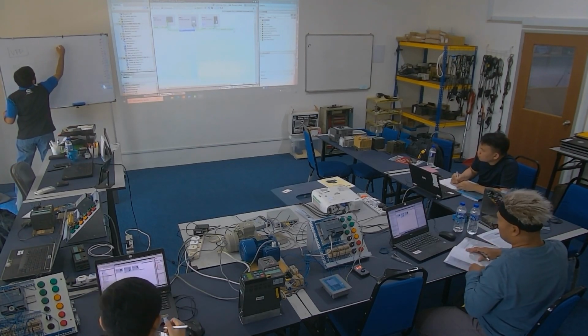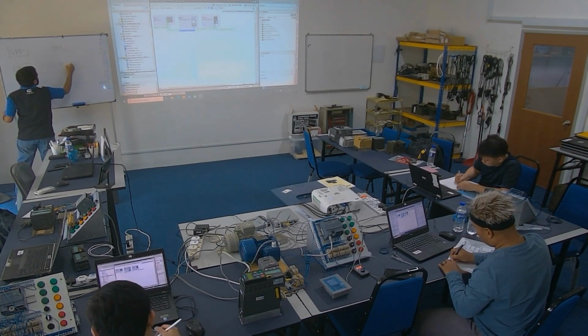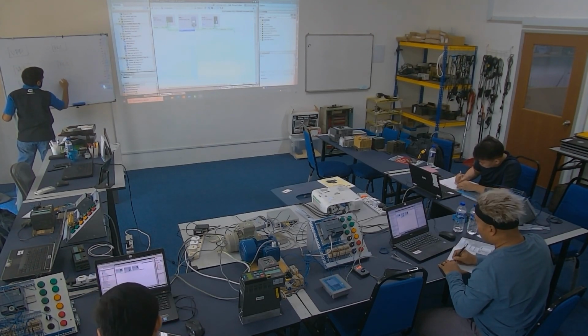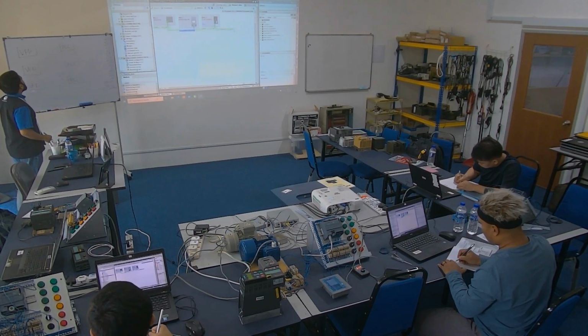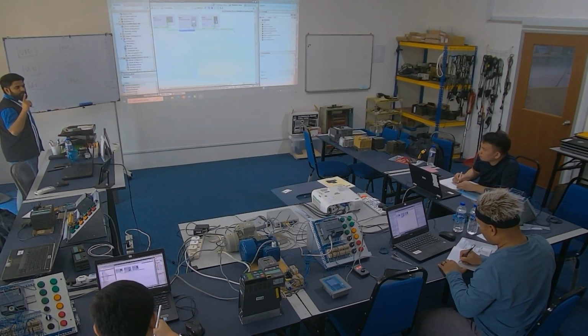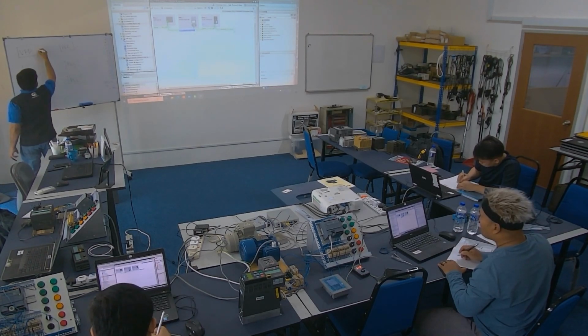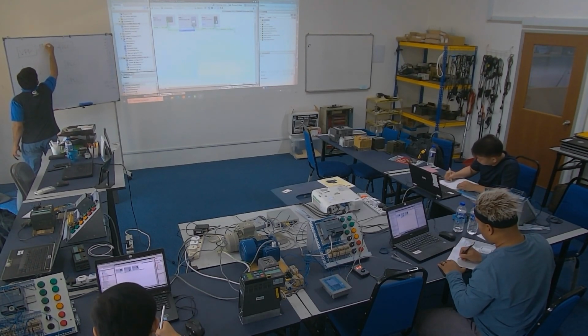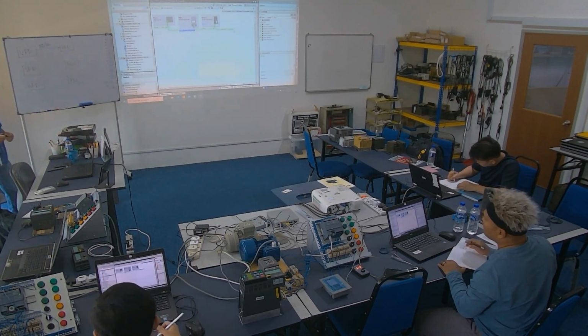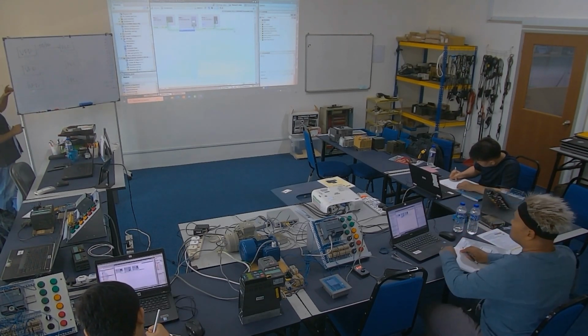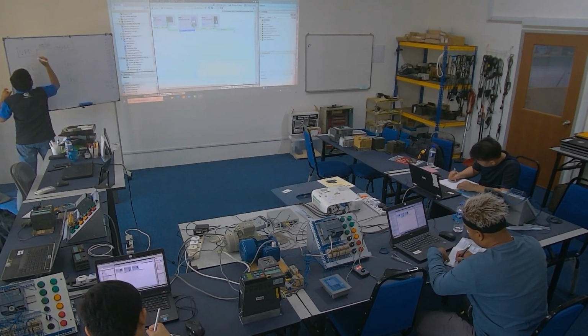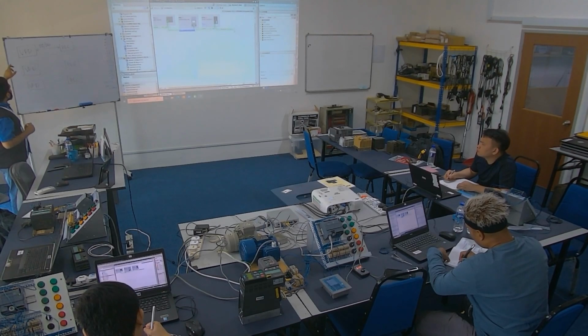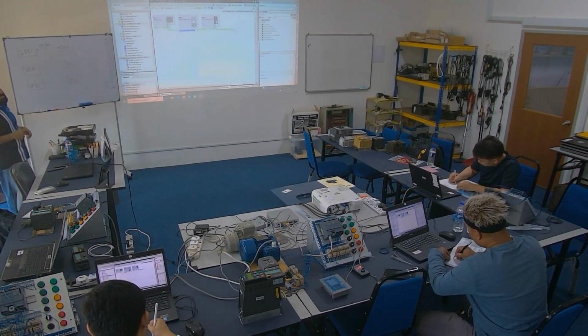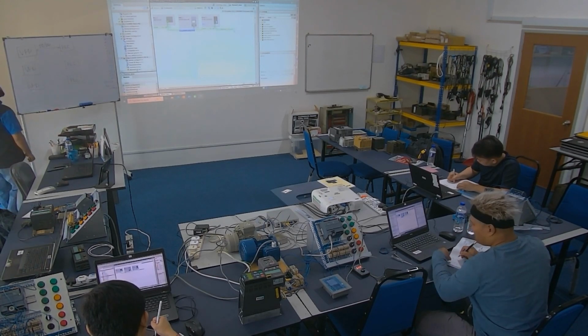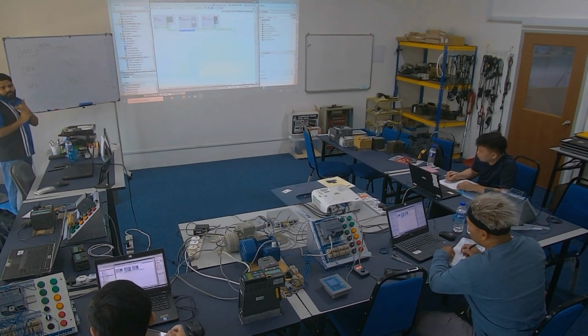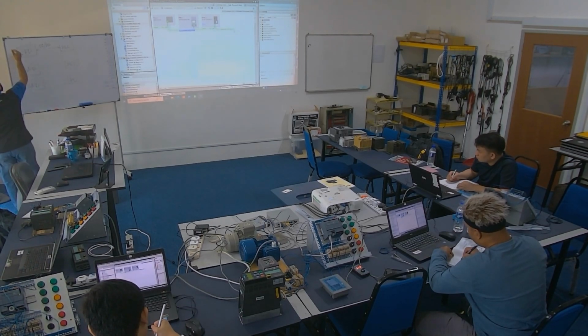So controlling using the PLC, right? Okay. The first way, okay, first way is controlling using DI DO. Okay. Digital input, digital output. Okay. So your PLC will control the VFD using the DI/DO only. So DI/DO means what? The PLC can just on and off.